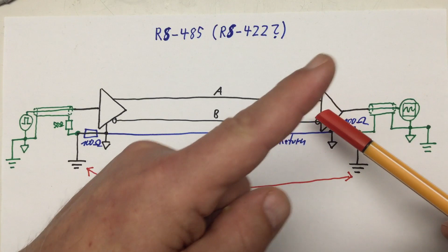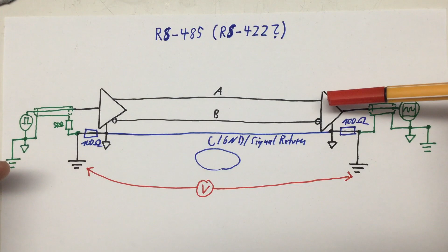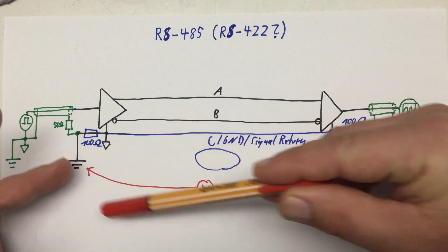In the last part, card here, link in the description, we talked about signal return path, grounding, potential differences, and so on. We discussed putting 100 ohm resistors in this configuration, where your transmitter and receiver are referenced to mains earth, to alleviate problems from currents induced by different potentials of your mains earth connections in the ground loop created when you run an explicit signal return line.